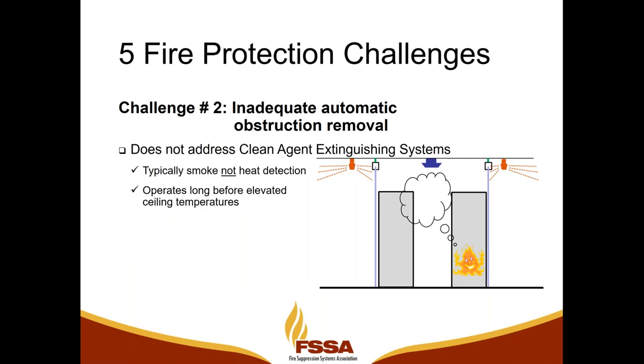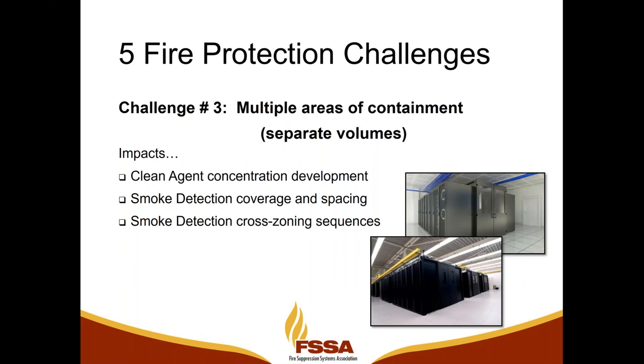With clean agent systems, we activate those systems off of smoke detection. Because we're going to activate when the fire is small, when we can just sense smoke, those barriers will not have been removed by heat, and they will still be in place. That will impact the distribution of the gaseous clean agent into that space. Another challenge created by aisle containment is that we basically build multiple volumes inside of the space. As we separate the larger volume into smaller volumes, that can impact the clean agent concentration development, the smoke detection coverage, and our strategy for releasing the clean agents when we use cross zoning or other confirming detection techniques such as counting zone sequences.